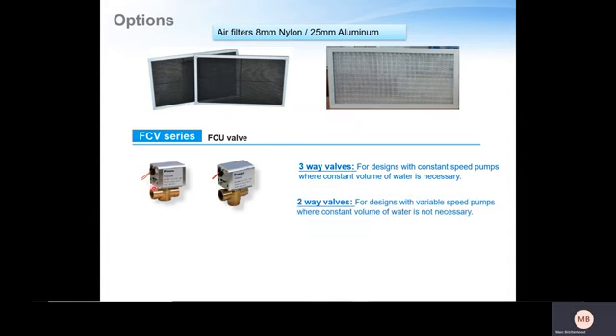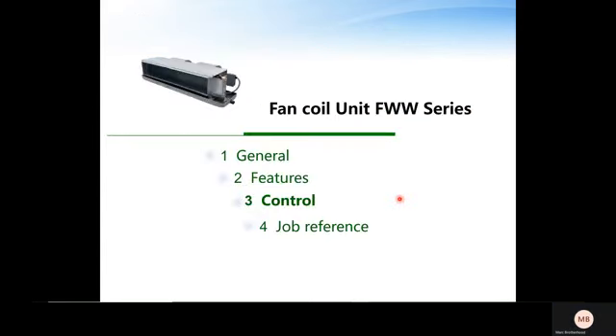A two-way valve, these are often also on very large systems, but these are for designs where you have variable speed pumps in the plant room and where constant volume of water isn't necessary. So this is like an on and off, there's no bypass of water. So it depends on the strategy. We can offer both, either the two-way valve or the three-way valve, with the electronic actuators driving the valve stems. What kind of control can we offer on these units?